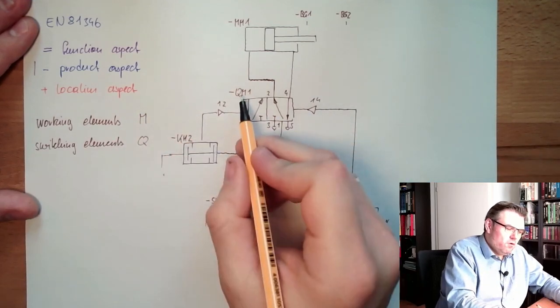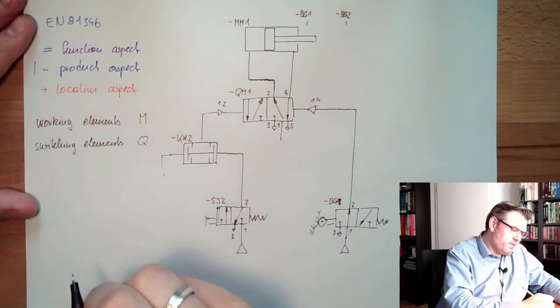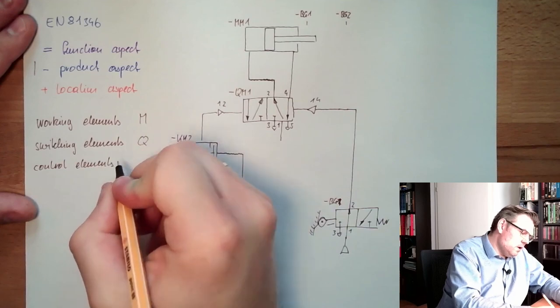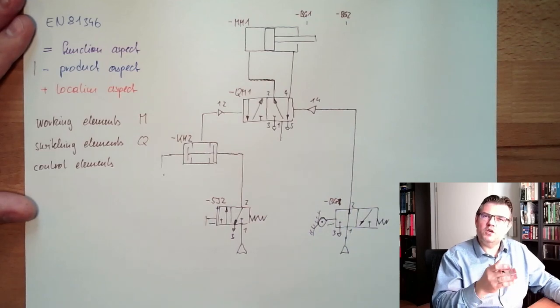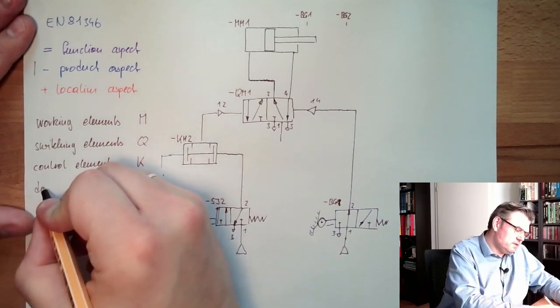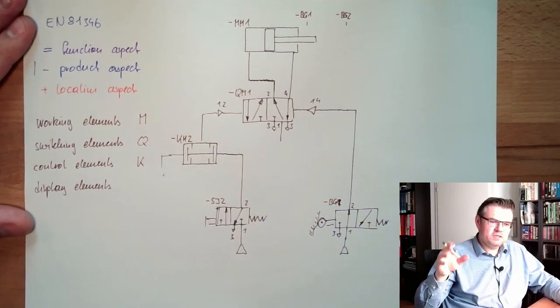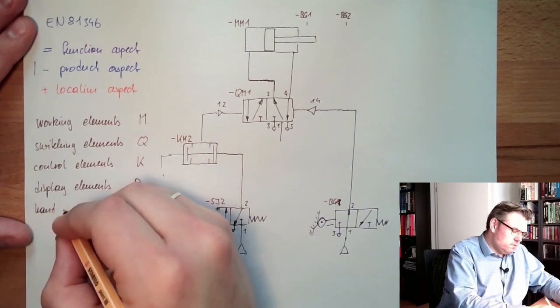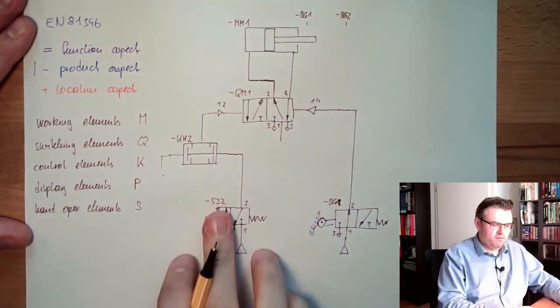They are really switching the energy to the working element. Then there are control elements. Those control elements do not really switch the energy, they're just switching information, informational content. These are the Ks. Then there are for instance displays, display elements like lights or displays, these are the Ps. And then there are hand operated elements, these are the Ss.